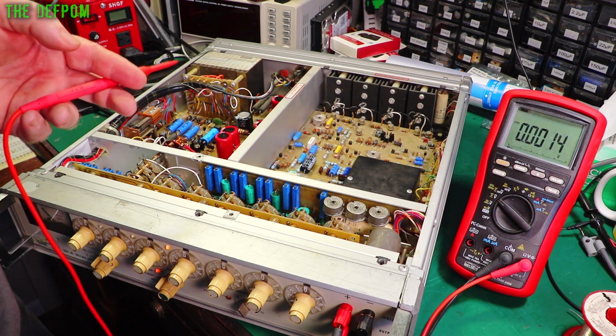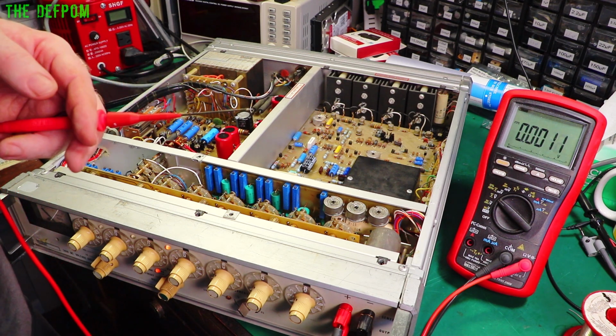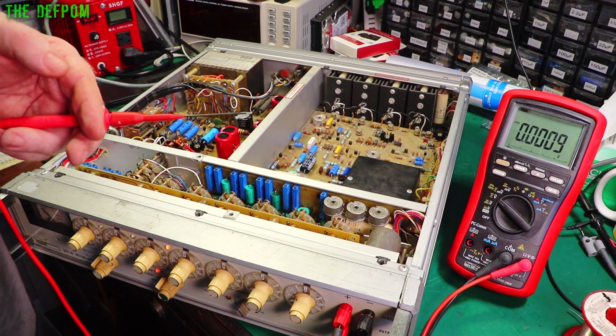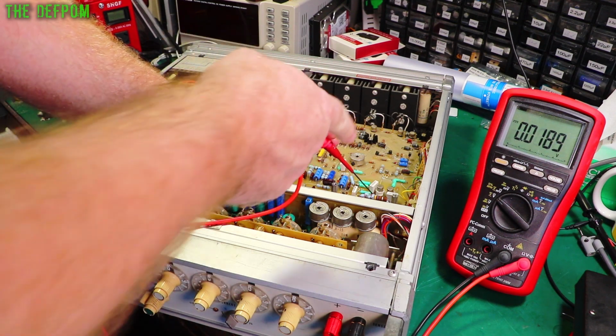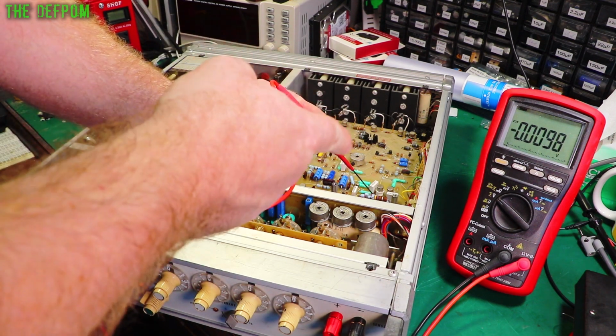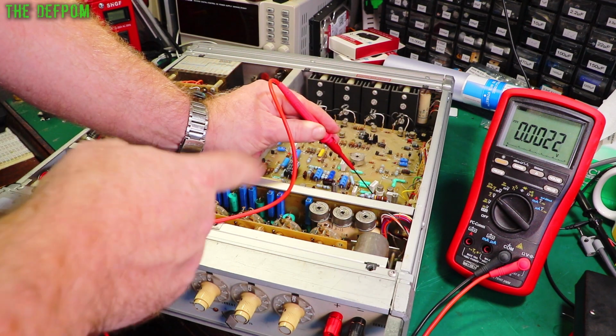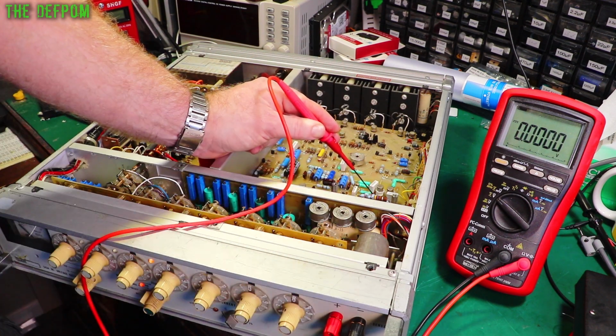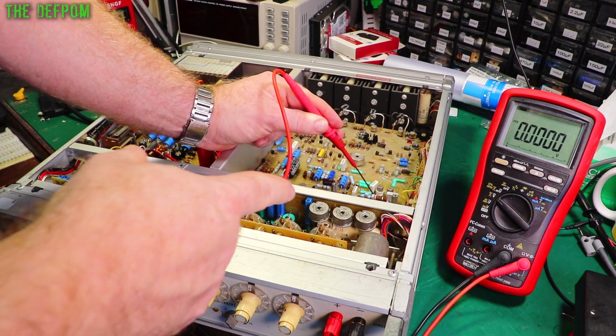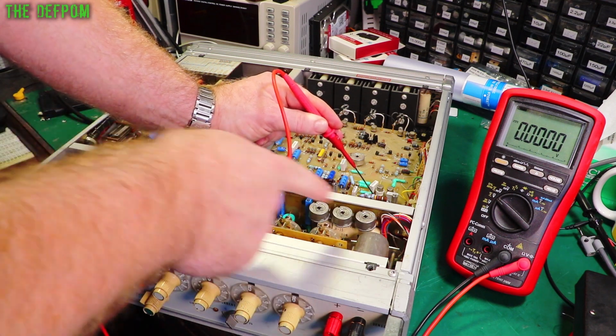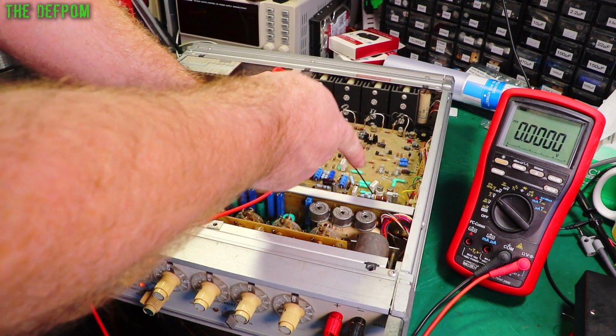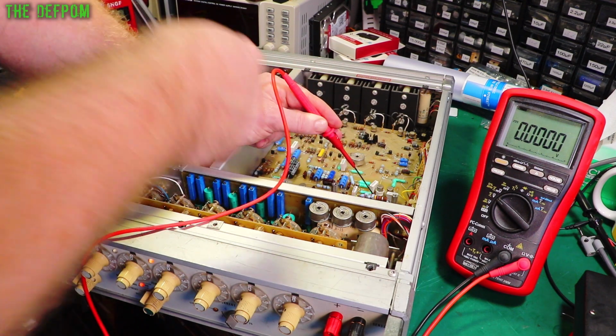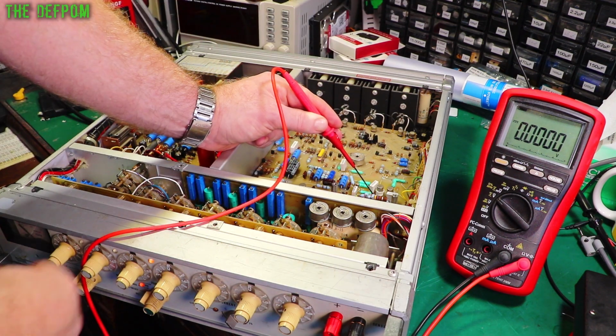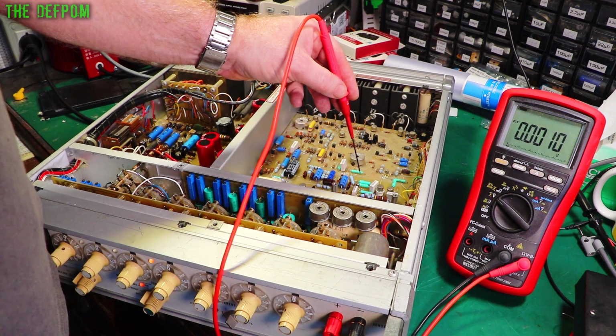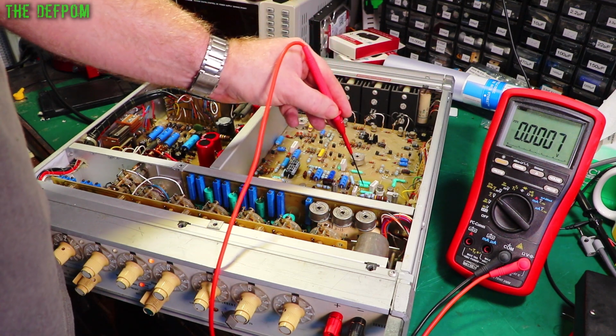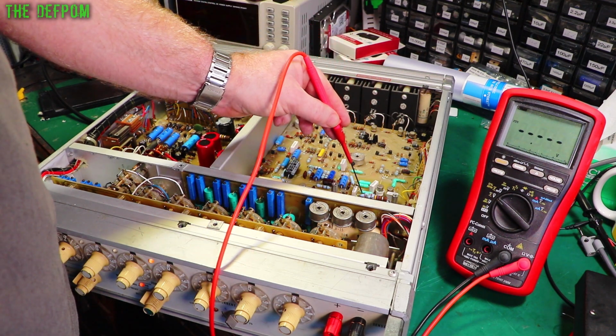Is it sensing incorrectly? Maybe it's a divider problem. Maybe it's a switch problem. So what I'm going to do now is just measure here at R17 and R171, which is normally inside this covered section. This is the return from the sensing strings and stuff like that. So I have to go through the switches and go to these precision resistors. It comes up over here, which then goes all to the chopper amp and everything like that. It's like the input feed for that. So this is where it senses what the voltage is. This is the one underneath that plastic cover, and that is the input from the sensing string.